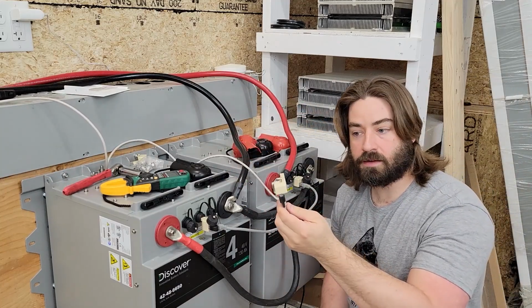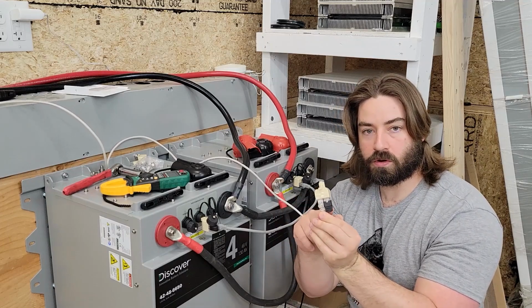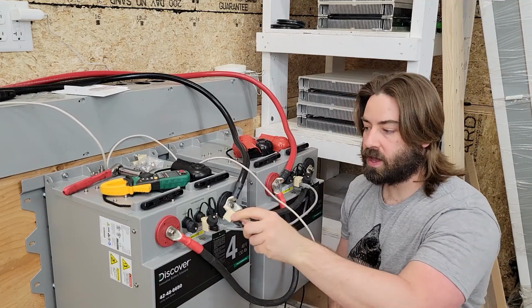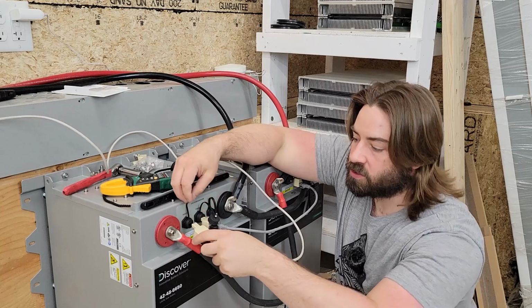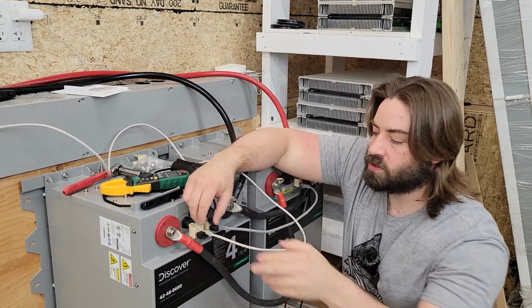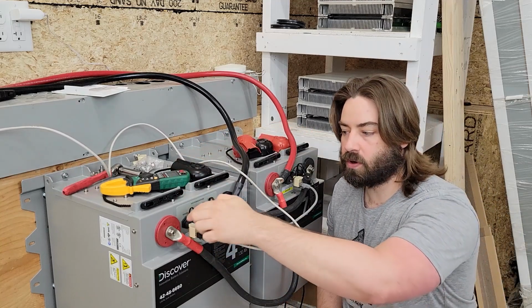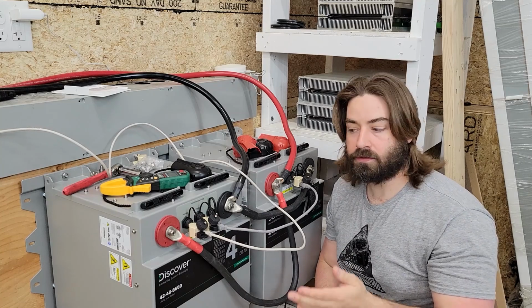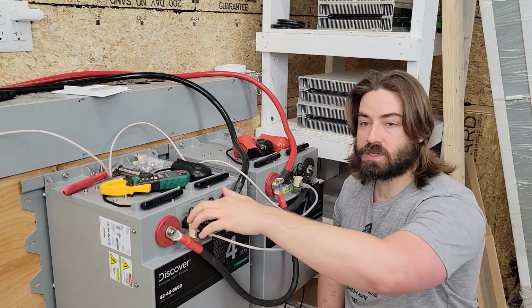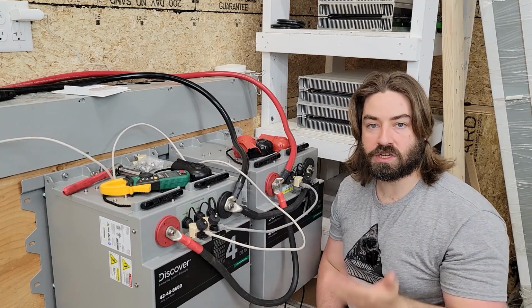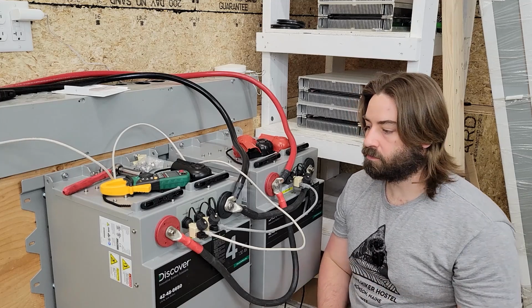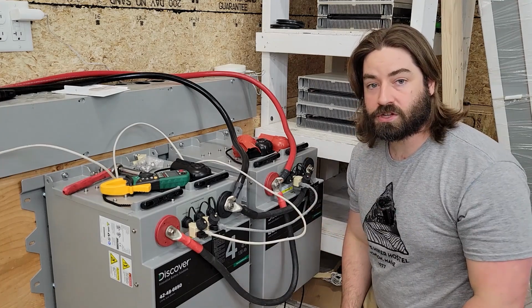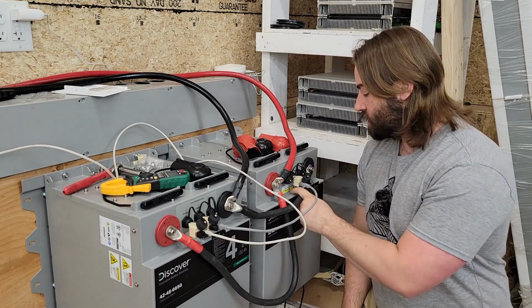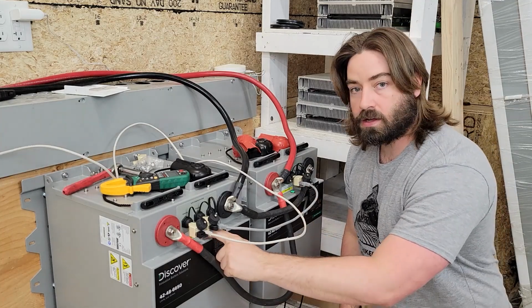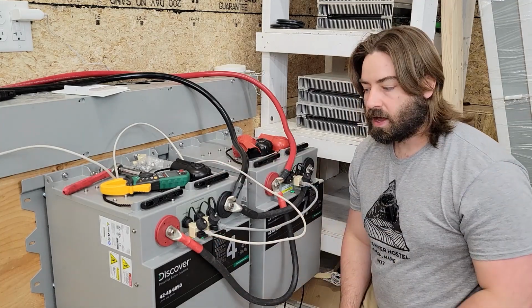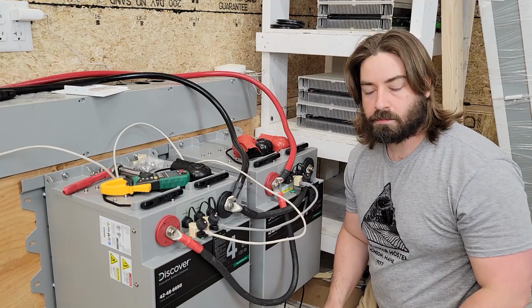In this case, I have one more splitter with one more terminator and the Cat5 wire going up to the Schneider. That's on the Xanbus port. It's still an RJ45 port, but that's specifically talking Xanbus, which is the Schneider proprietary system. The circuit breaker of the Schneider is on, and I'll just press the little power button and turn on the batteries. I don't think the order of how you turn them on matters.